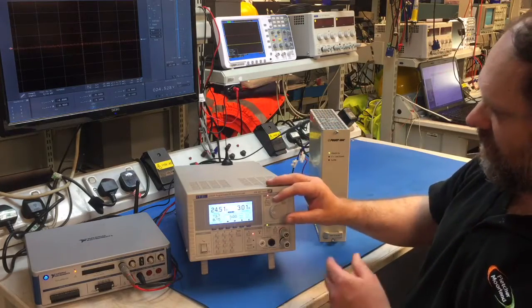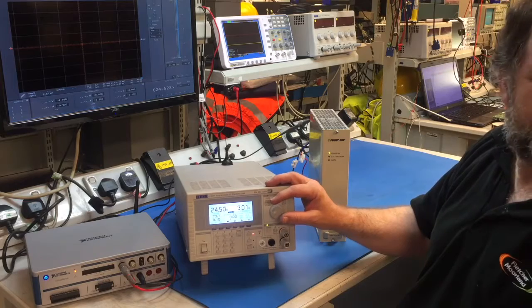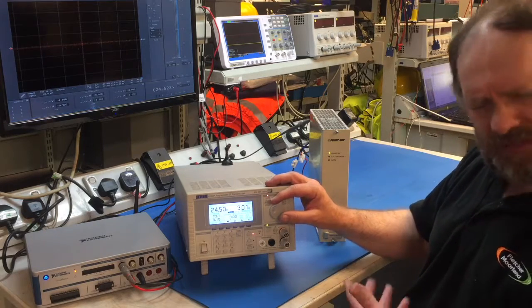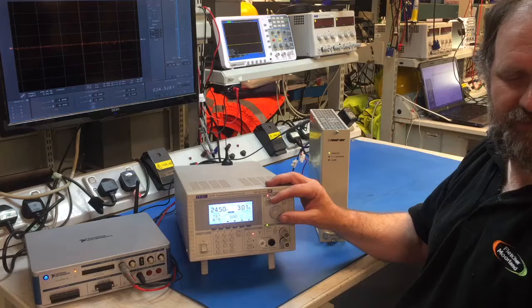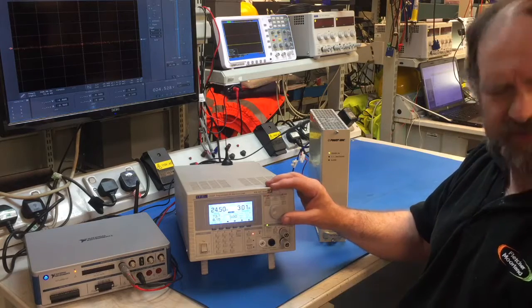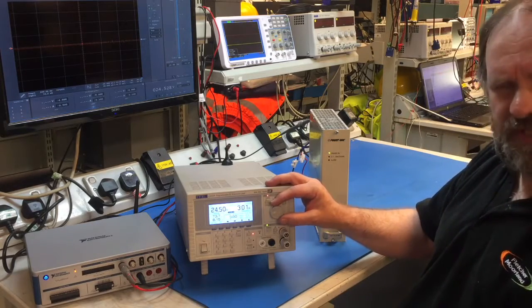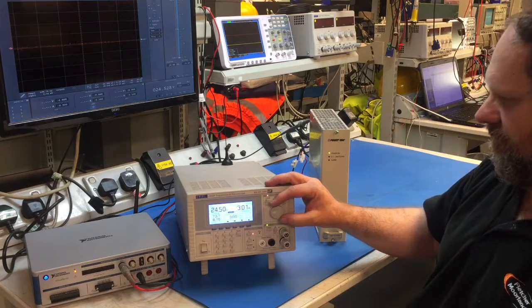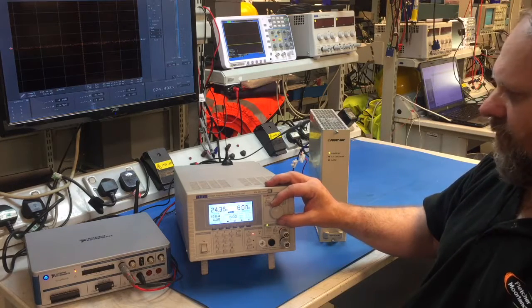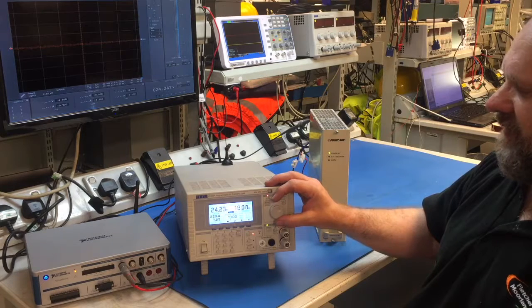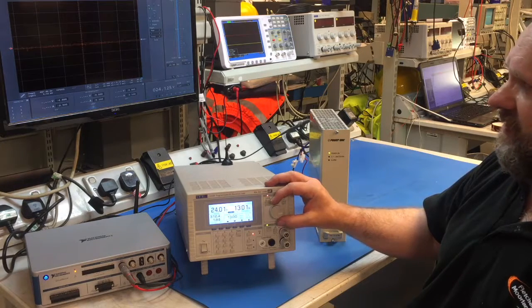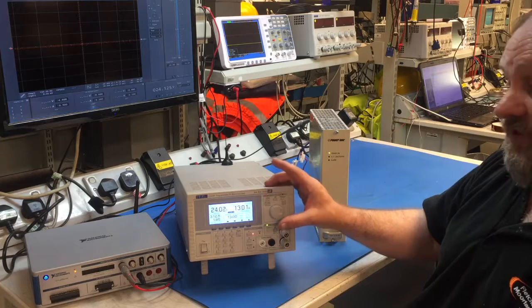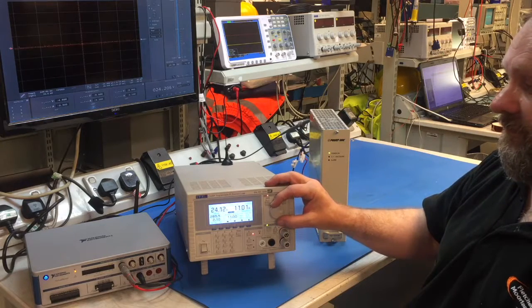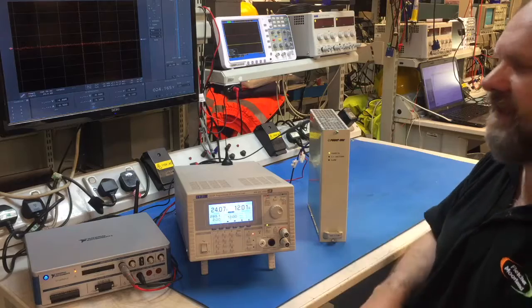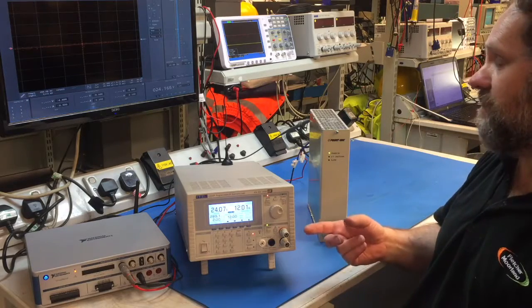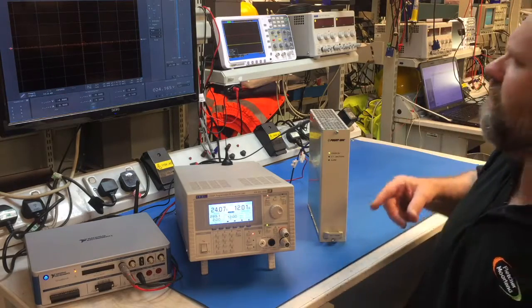What we're going to do is increase the load from 3 amps all the way up to 12, then to 12.5, just taking it slightly into overload to make sure it can cope, and back down to 3, in 1 amp steps. What I'm looking for is not a very large change in output voltage, which would be correct behavior. We'll take it to say 13 amps, back down to 12, and leave it there a little while to make sure the power supply performs accordingly while I take some measurements.